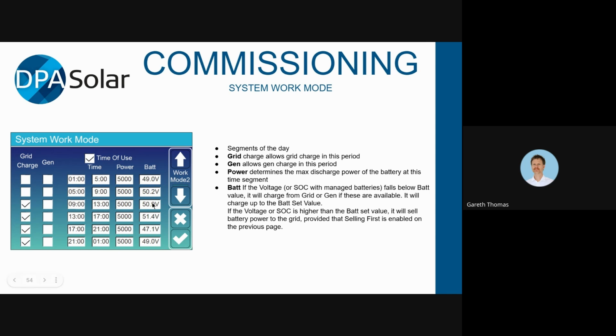And in the same way, if you get quite a lot higher than this, it will sell battery power to the grid, provided that selling first is enabled on the previous page. The way I've got one set up here in the office is that I have selling to the grid enabled in the evening, and I have a very low value. That's because I don't have a meter in the main switchboard, so I just sell during the evening at a very low rate, just to offset whatever the office running power is when nobody's here, because during the day we're covered by the main solar.